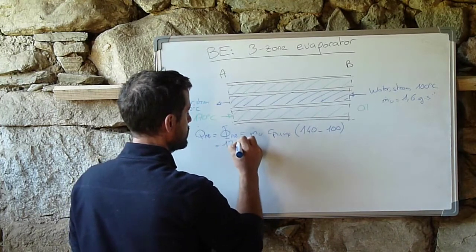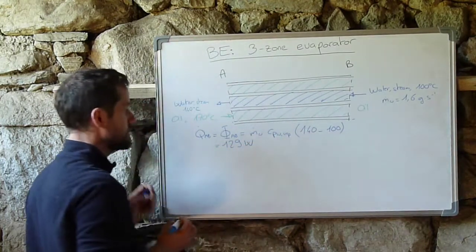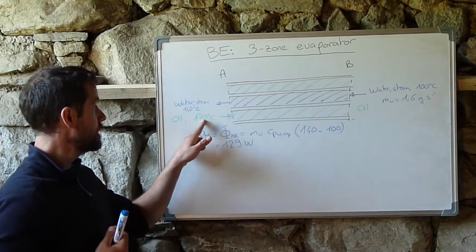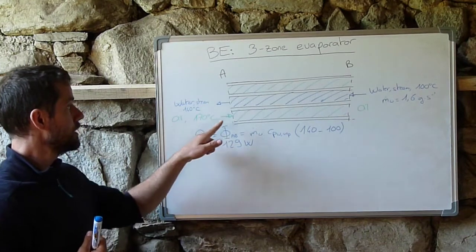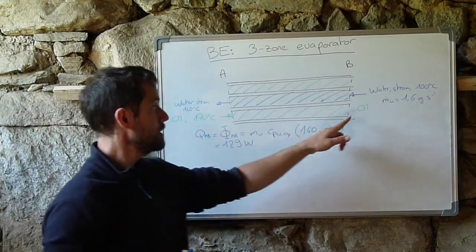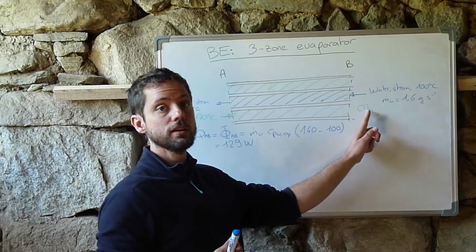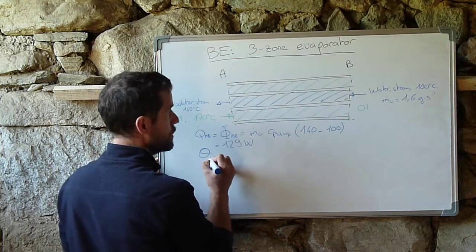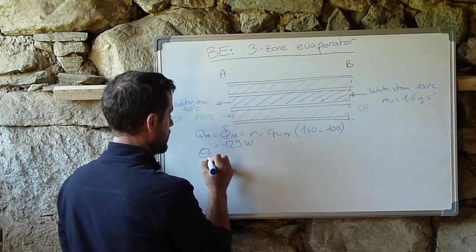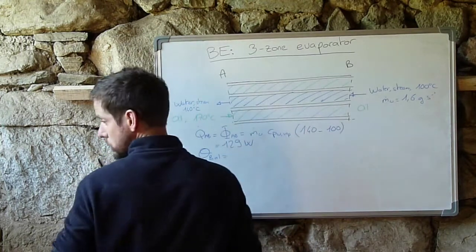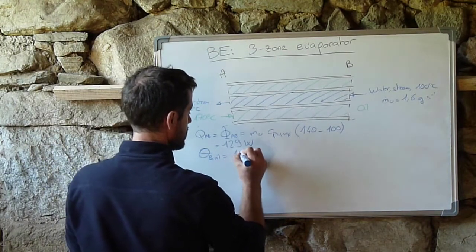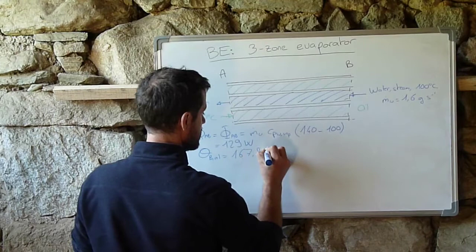So if you calculate, you have 129 watts for this first section. Once you know the heat flux, you can also do a heat balance of the oil that will be cooled down a little bit in this section in order to calculate the outside temperature of the oil. And if you do this, the temperature at point B for the oil is equal to 167.8 degrees Celsius.